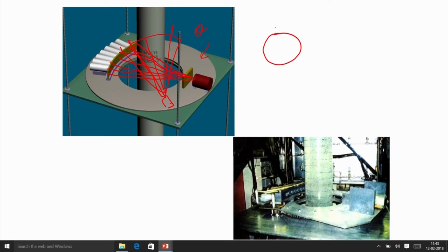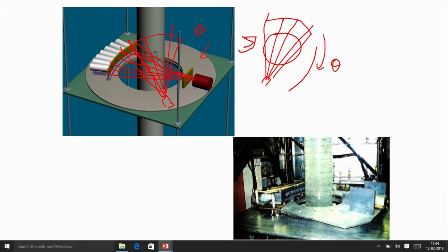Okay. So, in this way if I put a source, if I put detectors here, I will see the first scan in this way, then this whole system will move at an angle theta. The source will move here, the detector will move here, and again you will see the scan. Okay. So, similarly you will do it for different theta, and you will get the line average for each line, each detector, and that line average information can be reconstructed back to the pixel information.